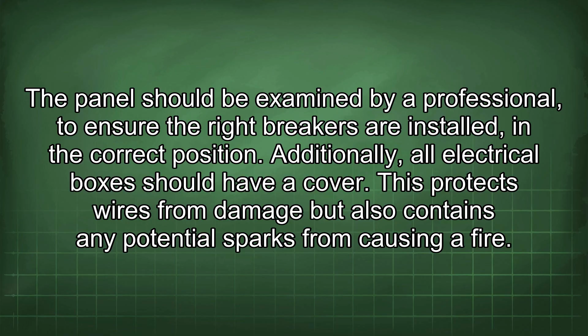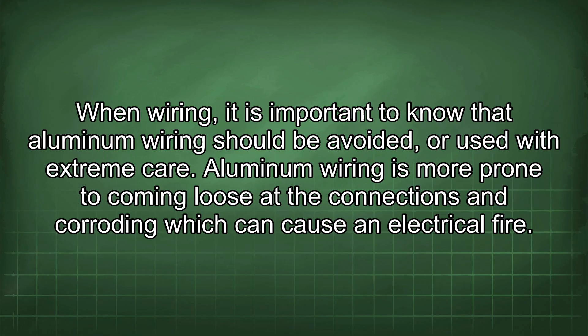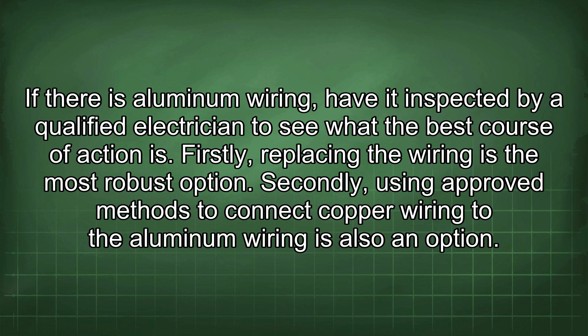When wiring, it is important to know that aluminum wiring should be avoided or used with extreme care. Aluminum wiring is more prone to coming loose at the connections and corroding, which can cause an electrical fire. If there is aluminum wiring, have it inspected by a qualified electrician to see what the best course of action is. Firstly, replacing the wiring is the most robust option. Secondly, using approved methods to connect copper wiring to the aluminum wiring is also an option. These methods involve using special connectors and compounds that prevent corrosion.